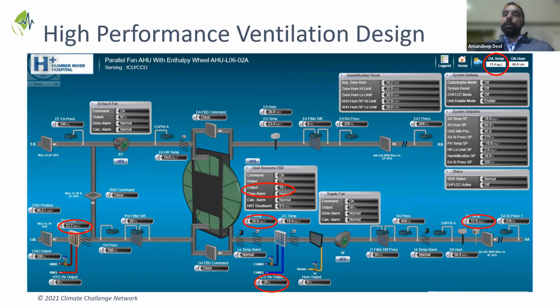The enthalpy wheels had to perform to an exceptional level to get those results. Two things building operators did, which we got shared for them, differentiate this building among others we're currently looking at through the Greening Healthcare research: the preheat set point on these heat wheels is actually lower compared to other hospitals, which helps maximize the heat wheel operations - because generally those preheats are set higher on other hospitals for some odd reason, which doesn't maximize the savings.